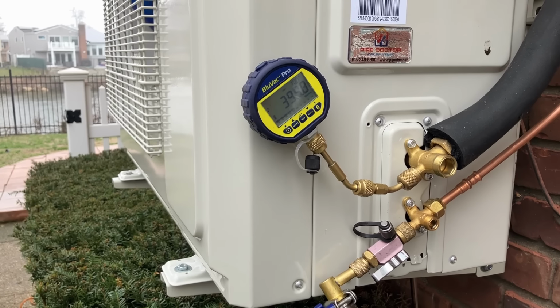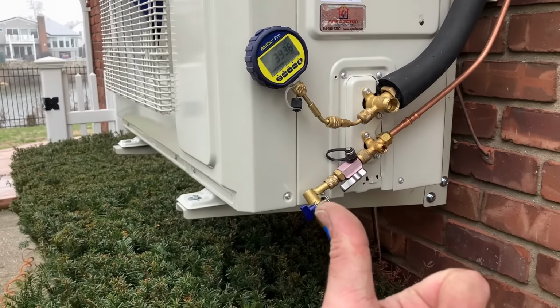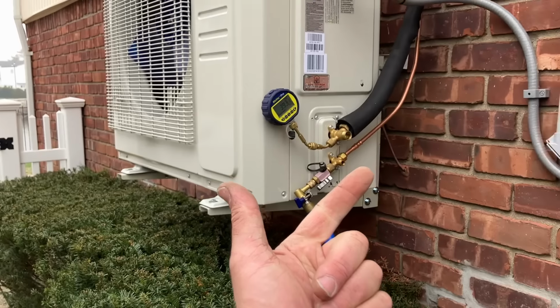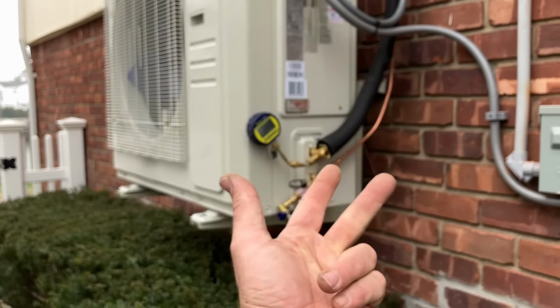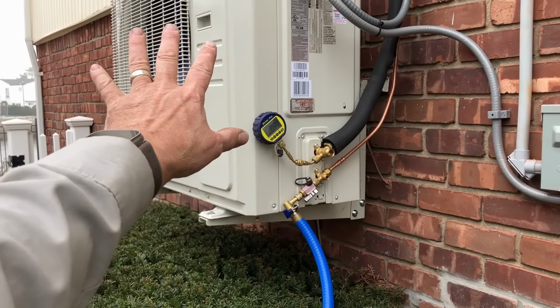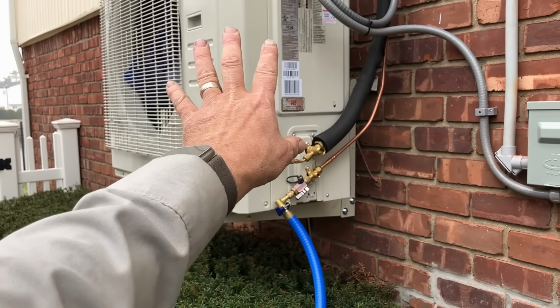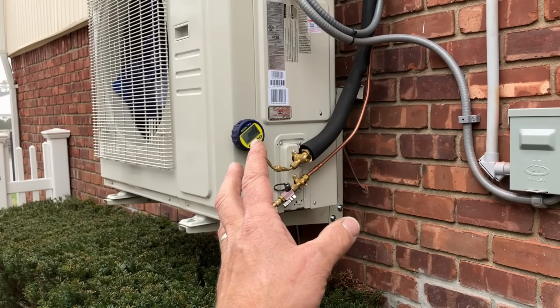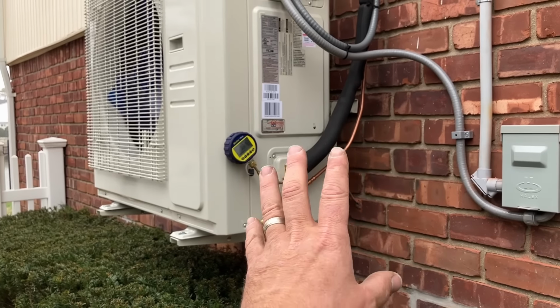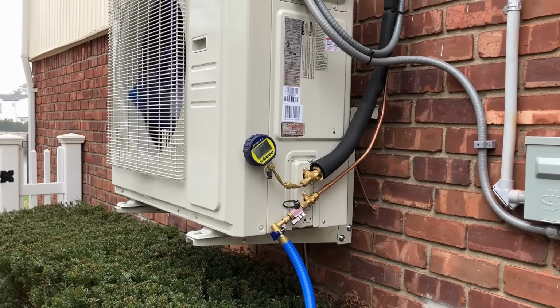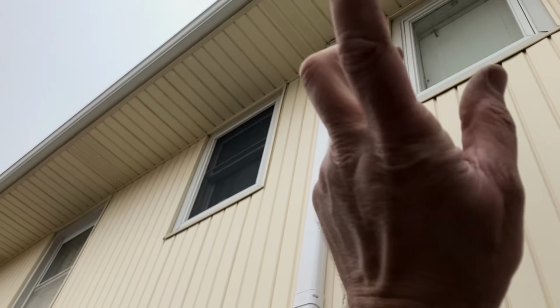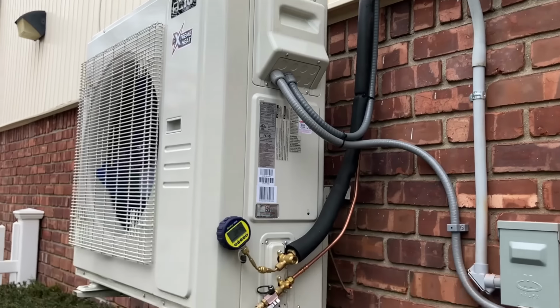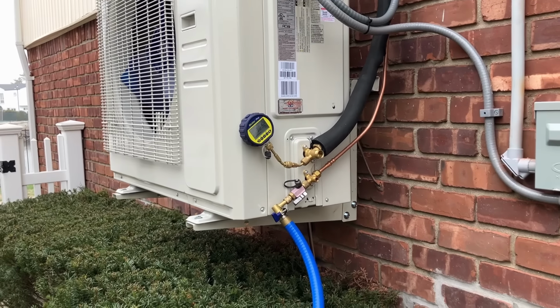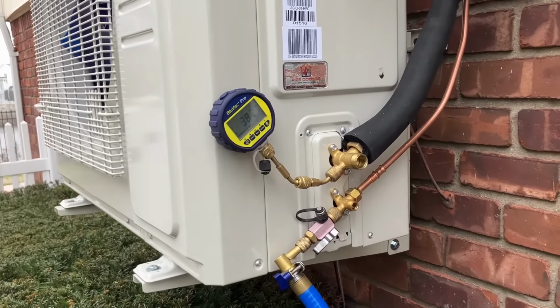Not bad, considering we have a 3/4 inch line set with 3/8, and an evaporator coil in the attic. This is self-contained, not opened up to the system. We're only vacuuming down approximately 30 feet of line set - up, across, and over, maybe 35 feet. Not too shabby.